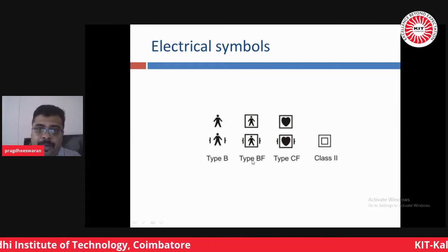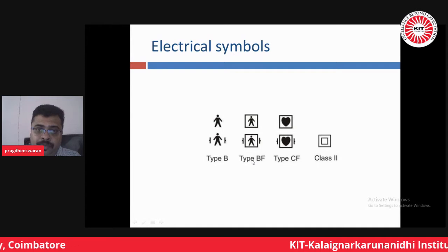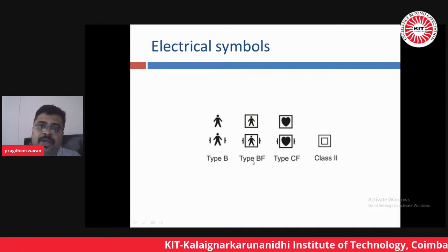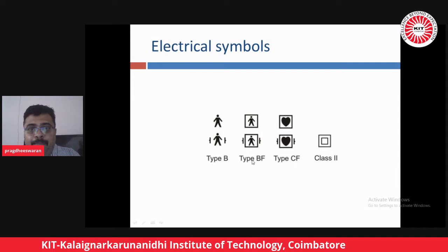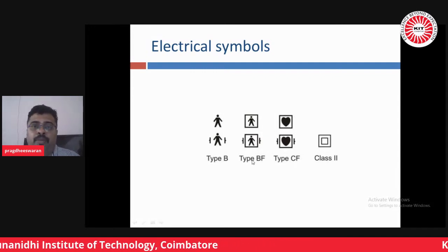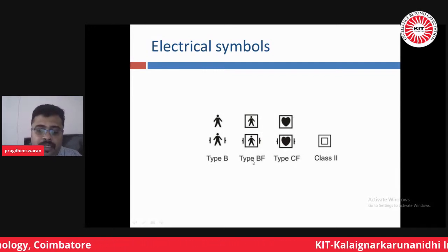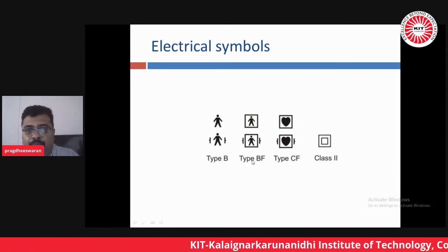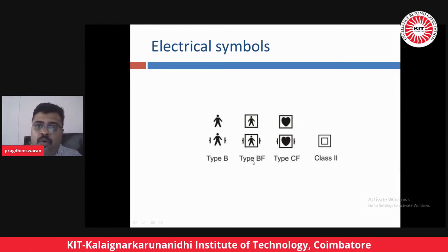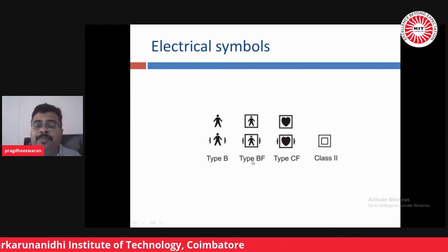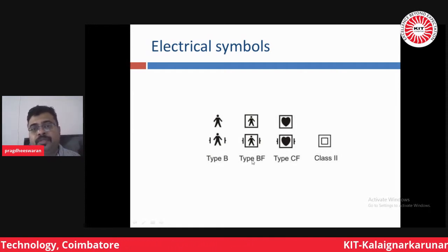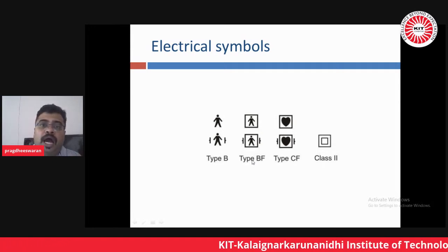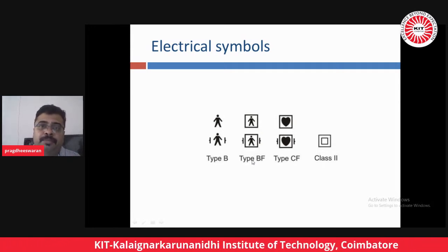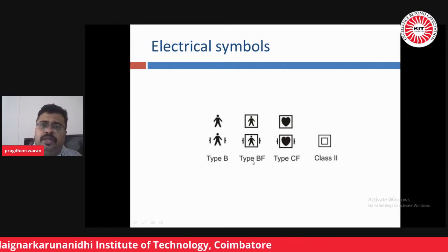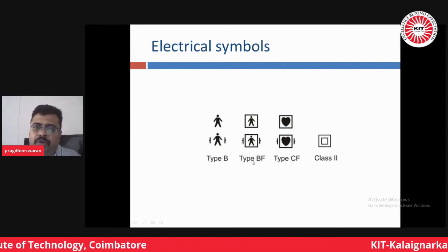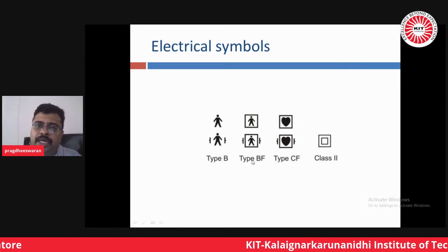Once the performance testing is passed, then do an electrical safety testing, or any safety testing defined as per the protocol for the machine. Then a pass certificate should be put on the equipment. It is not that we do a performance testing, put a sticker and pass the equipment. No. That is why the calibration procedures are costlier, because they have to do two procedures, and the calibration procedures are cumbersome. It is not that you connect the equipment and it gives you the report, you take it, print it out, sign it and file it.